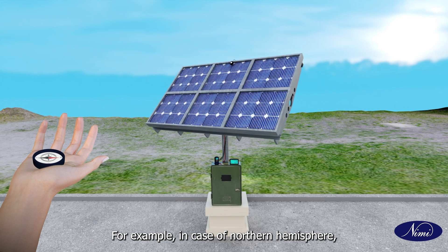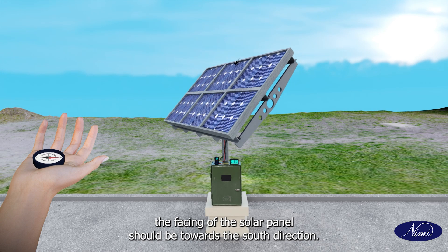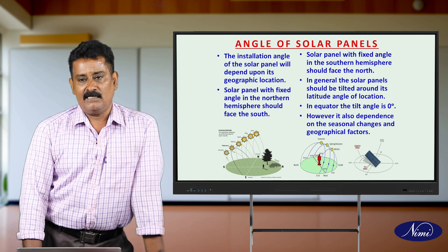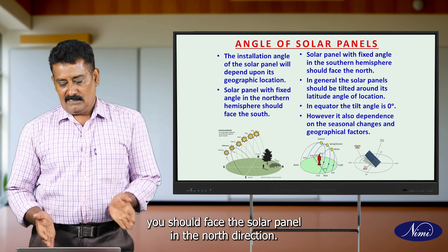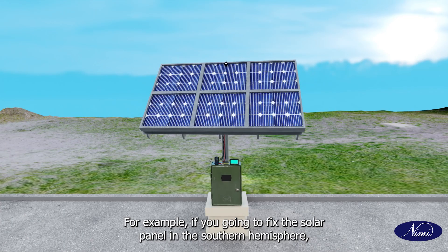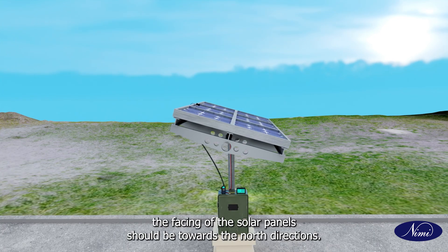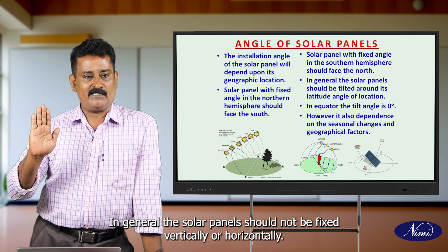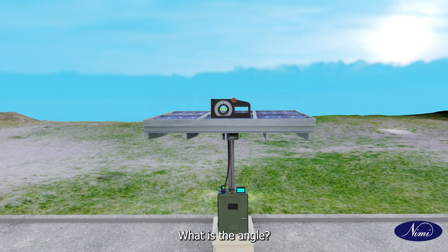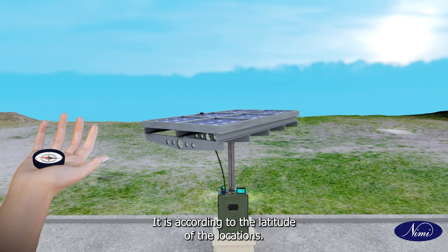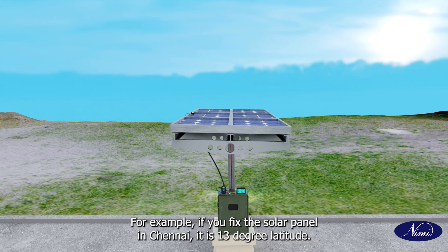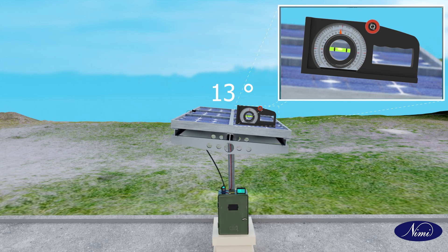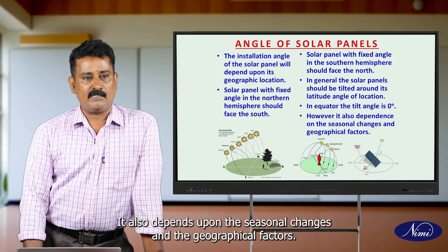In the case of the northern hemisphere, the facing of the solar panel should be towards the south direction. Similarly, if you are going to fix the solar panel in the southern hemisphere, the facing of the solar panel should be towards the north direction. In general, the solar panel should not be fixed vertically or horizontally — it should be fixed at an angle according to the latitude of the location. For example, if you fix the solar panel in Chennai, which is at 13 degrees latitude, the tilting of the solar panel should be 13 degrees. It also depends upon seasonal changes and geographical factors.